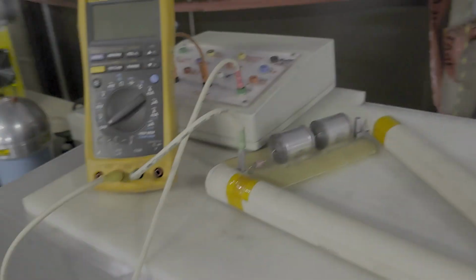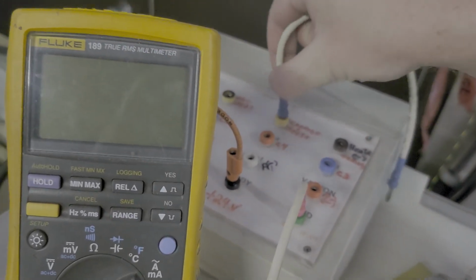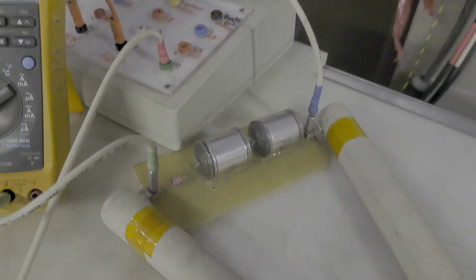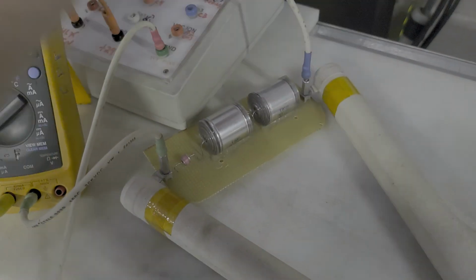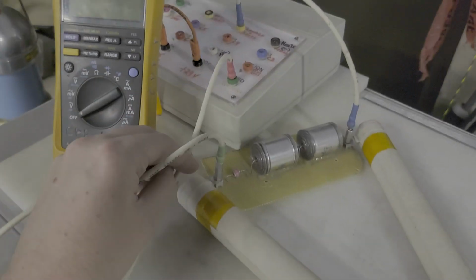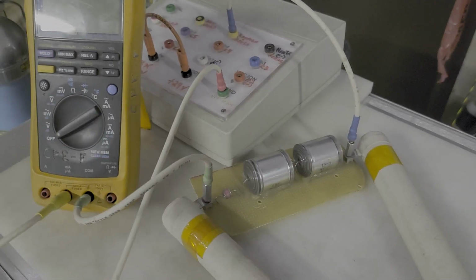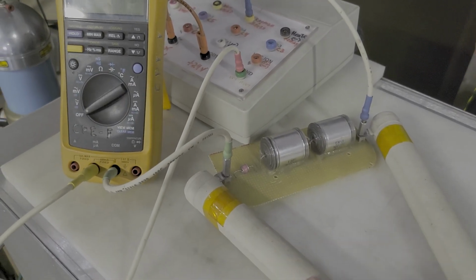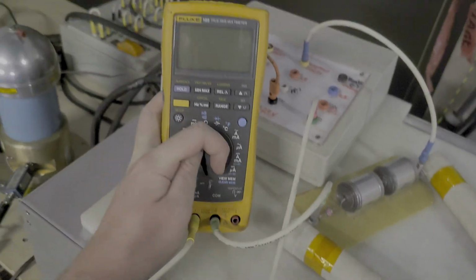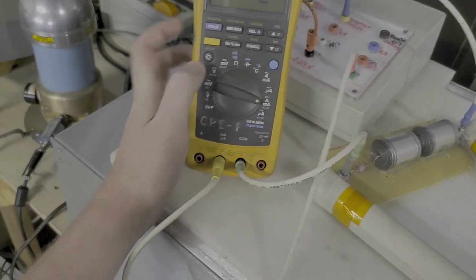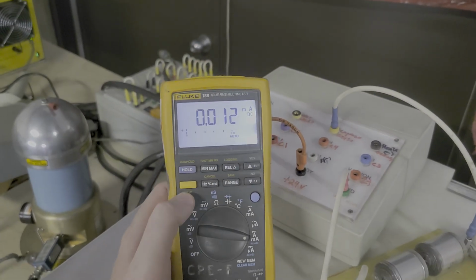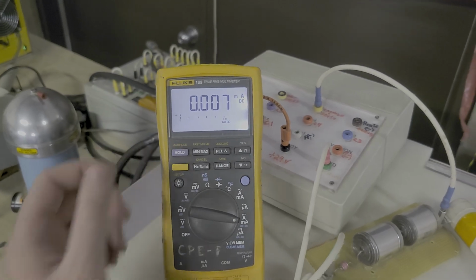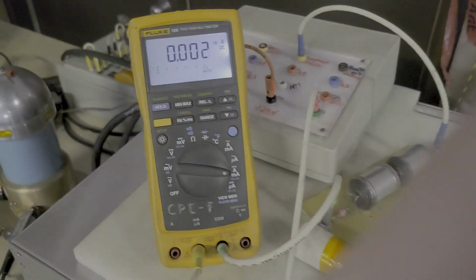Let's also wire up our cathode to the top of the load. And we're going to run this cathode at around 12,000 volts. So this will be running at 12,000. This will be at 0 across a 1.4 meg. We can do the math. But I don't want to because I'm terrible at head math. So let's turn this guy on. We see 0 milliamps right now with it off.